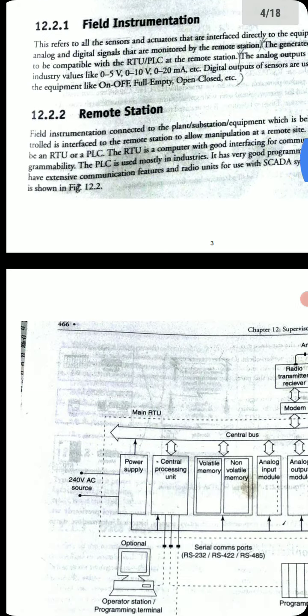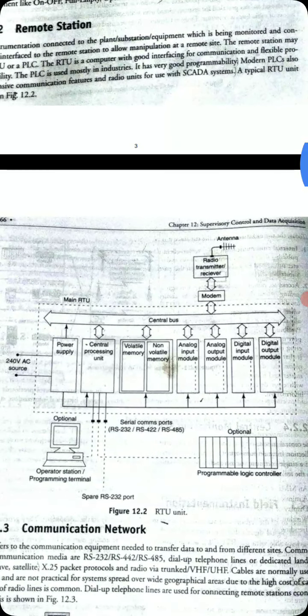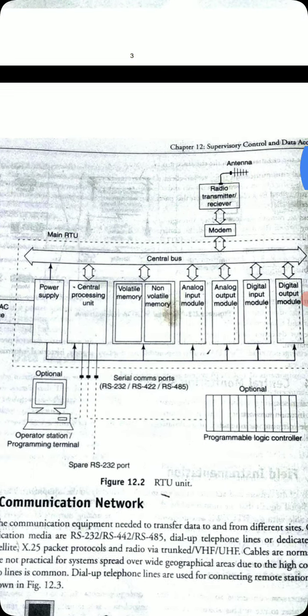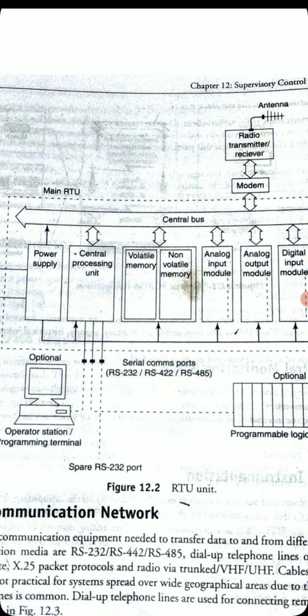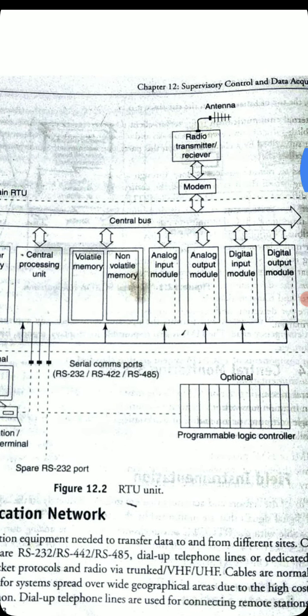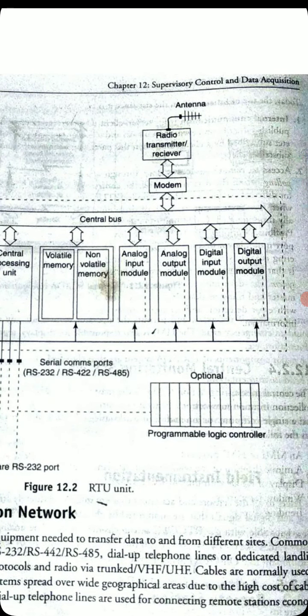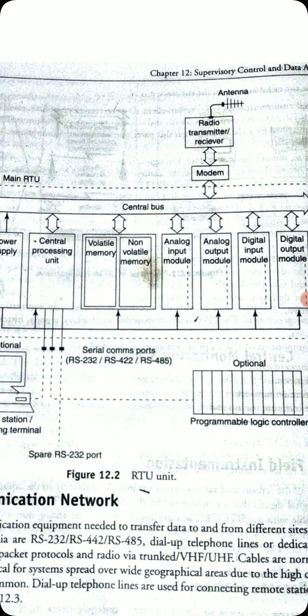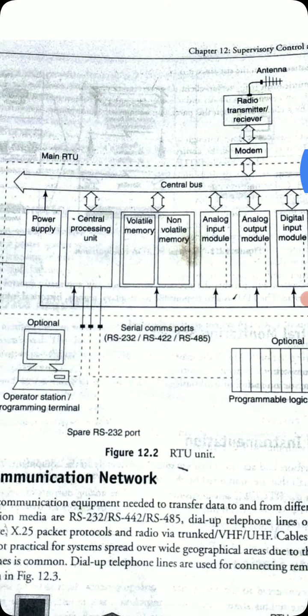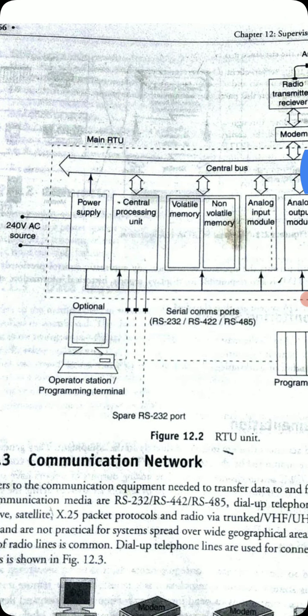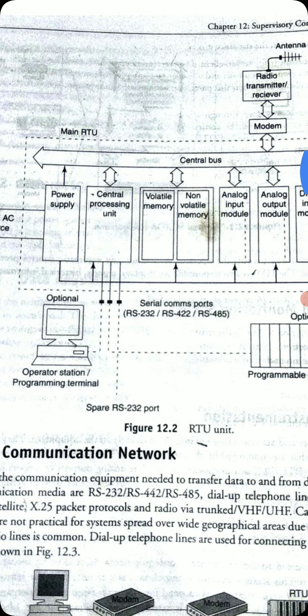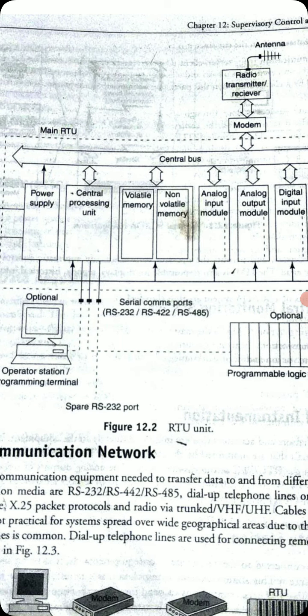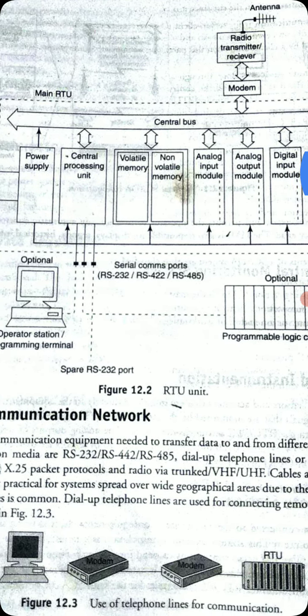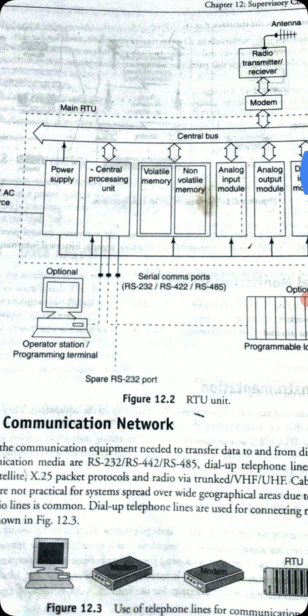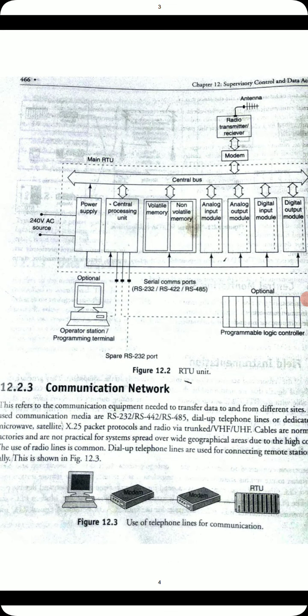The remote terminal unit figure is shown here. You can see there is a central bus where the power supply, central processing unit, different memories, analog input module, analog output module, digital input module, and digital output module are connected, and where the modem is connected. There is a radio transmitter receiver going through an antenna. The main RTU contains this and is given a 240 volt AC source. There is an operating station. See, a computer is there, and a programming terminal. Different cables are used for transmitting, and a PLC is also there. So this is a typical RTU unit, and this is how the remote terminal unit works.